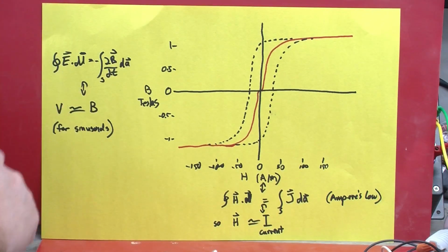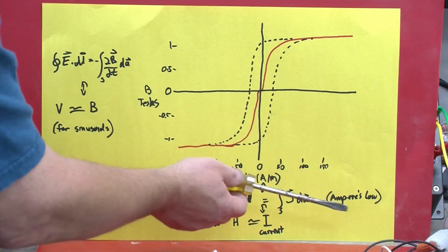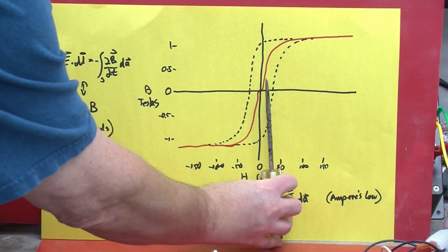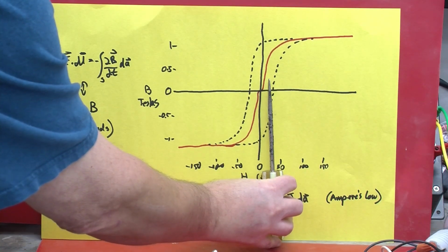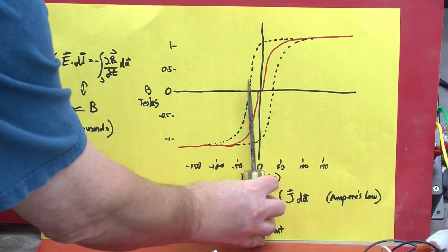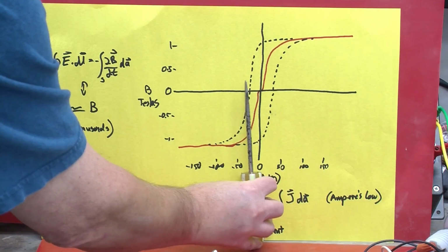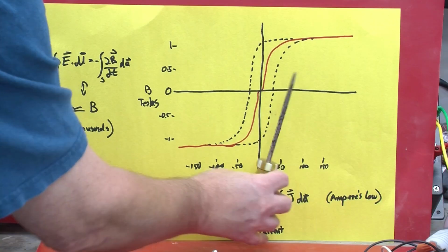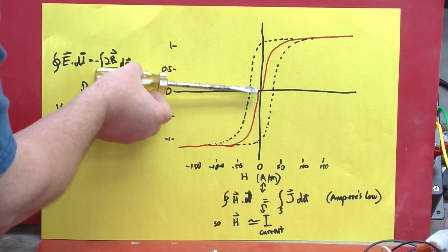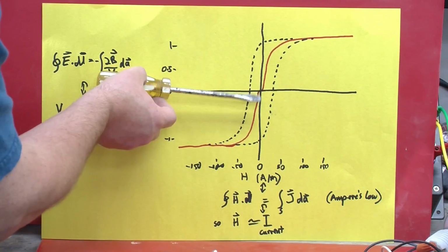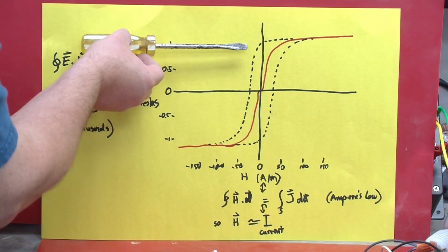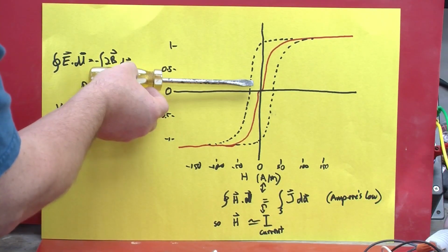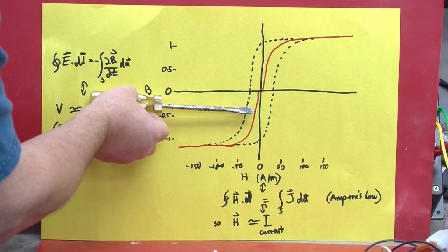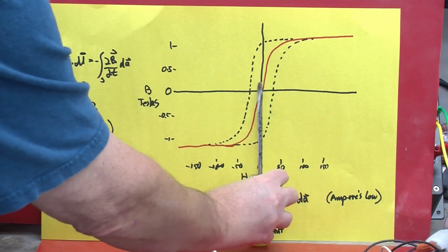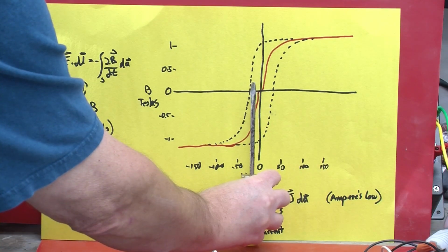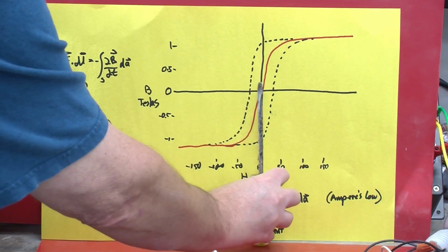So how does that apply to what we've been doing? When the transformer is operating normally, the transformer, or in this case really just an inductor, operates in this nice linear region where a small change in current produces a large change in voltage. That large changing voltage has to correspond to the 120 volts going into the coil, and if we work backwards, that tells us exactly what current we see going into the coil at the same time.